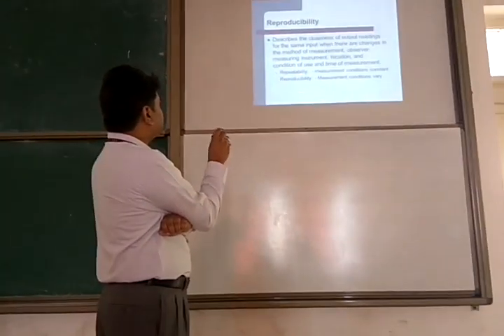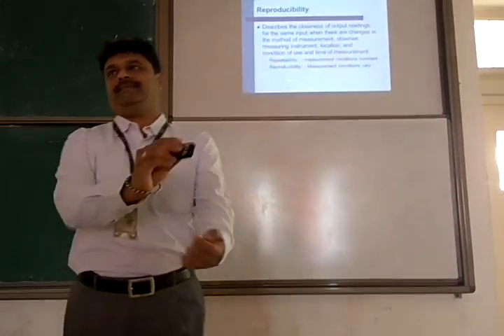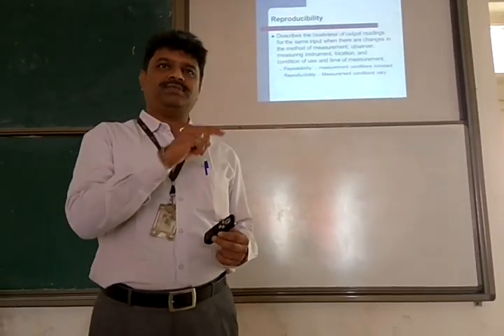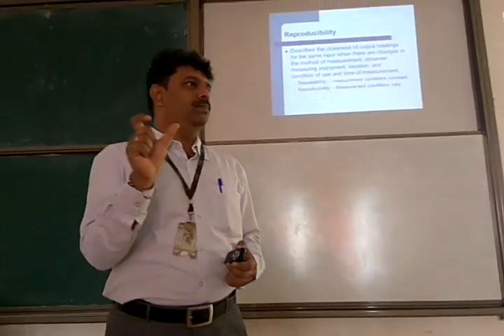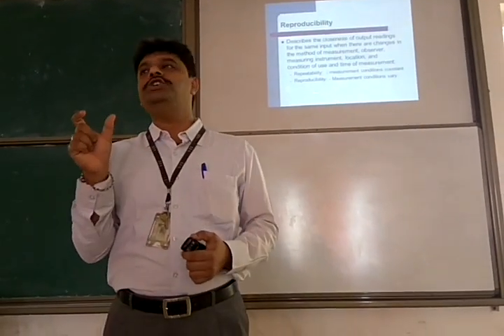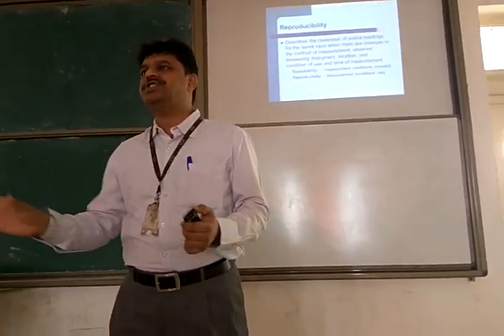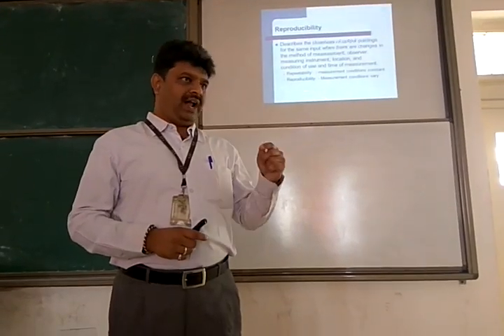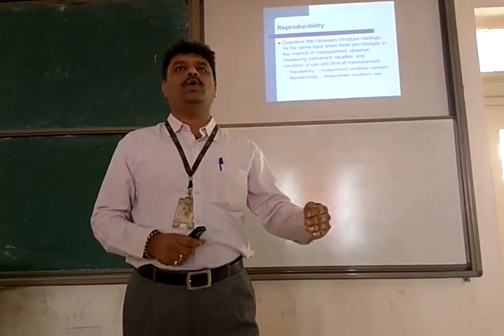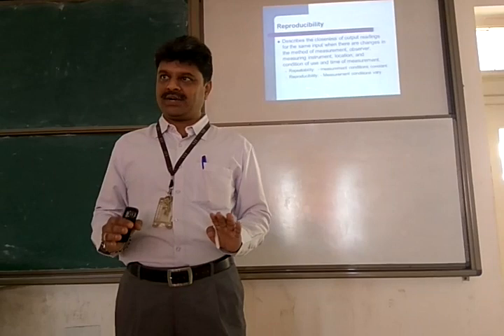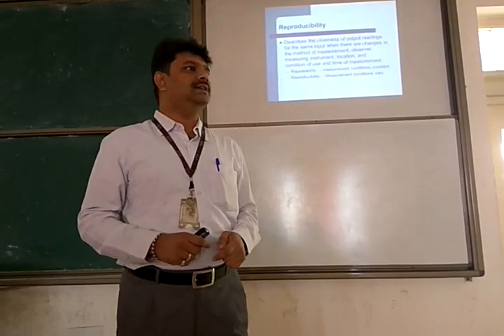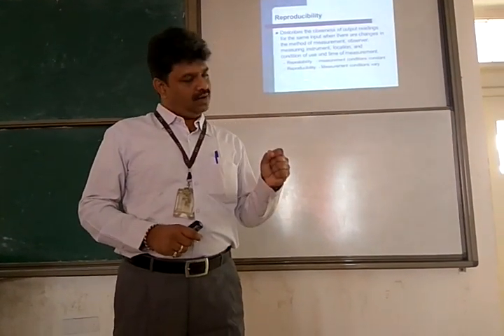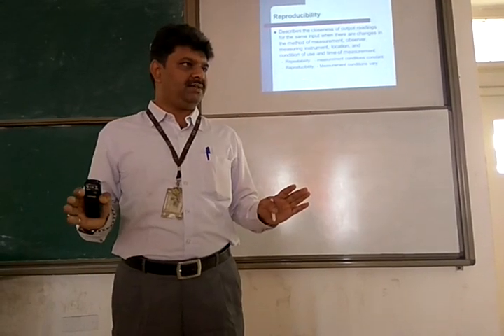Allow the measurement conditions to vary, and you call it reproducibility. Both these terms are for a short period of time—you take readings in a short period of time. If measurement conditions are varying, you call it reproducibility; if measurement conditions do not vary, you call it repeatability. Is this clear so far?